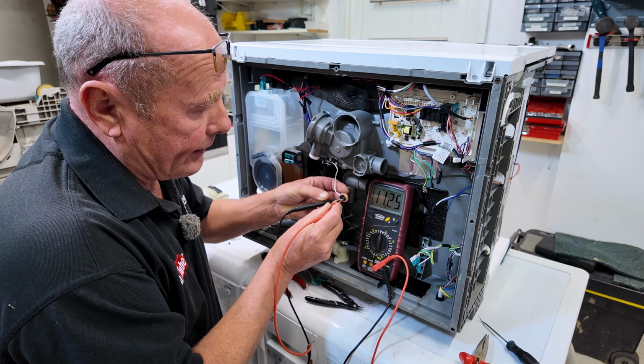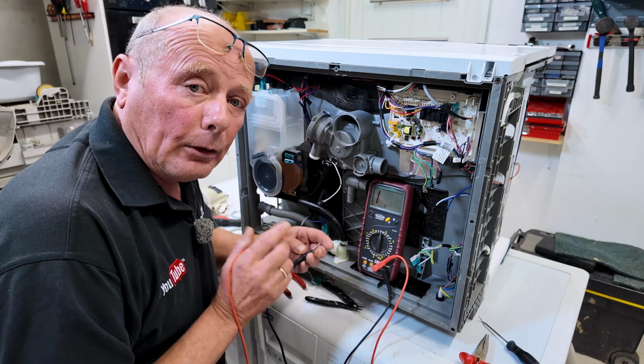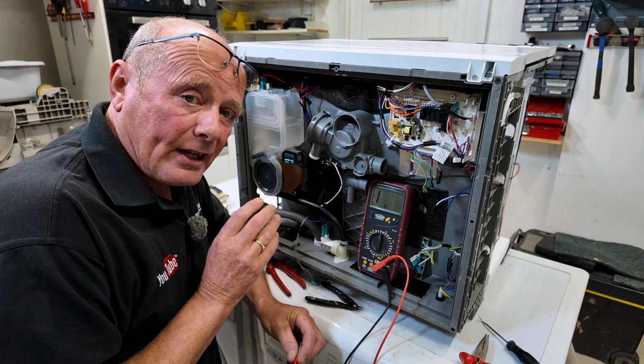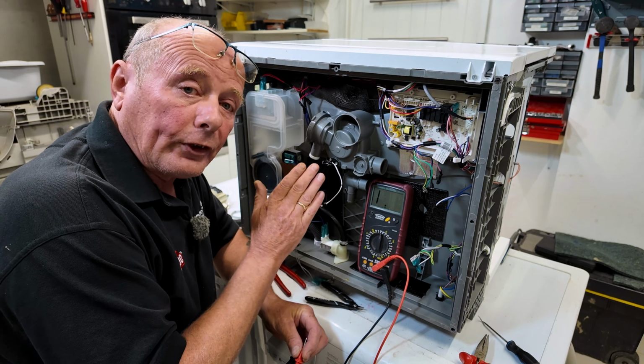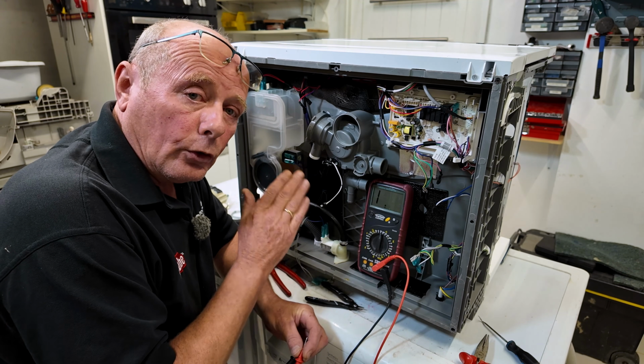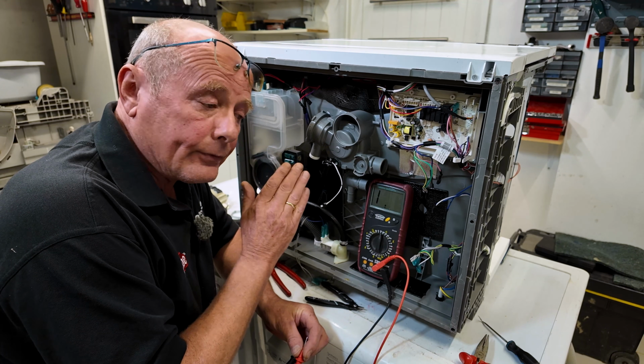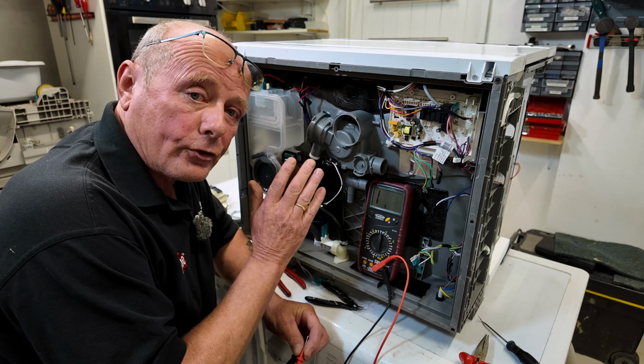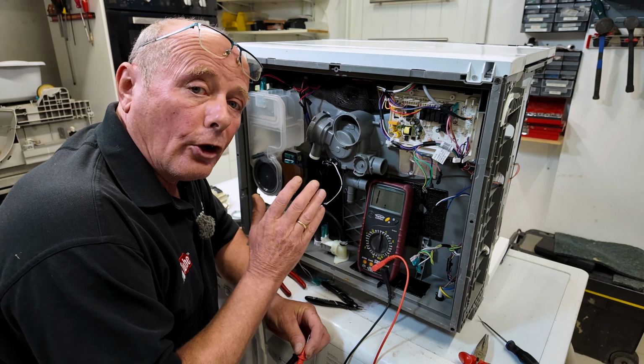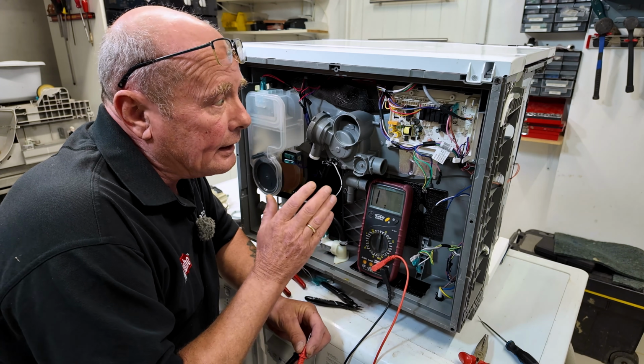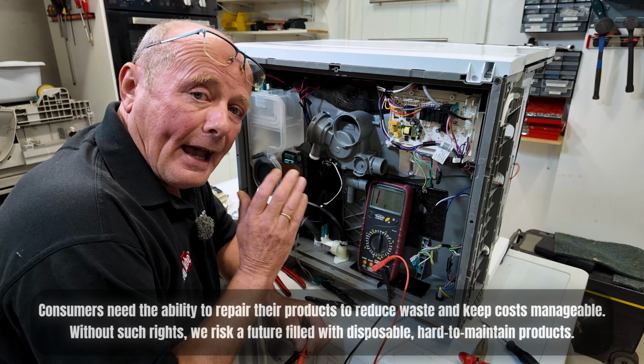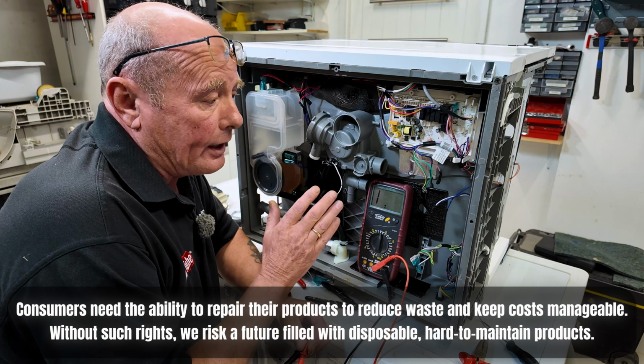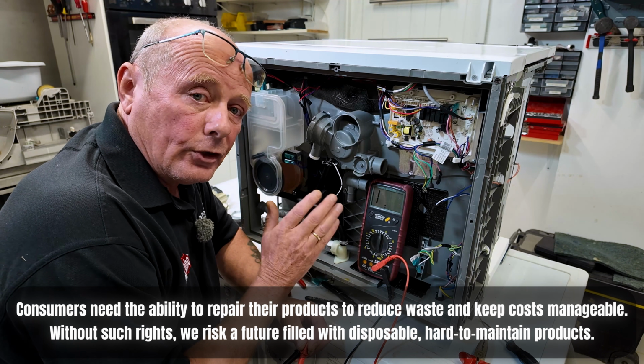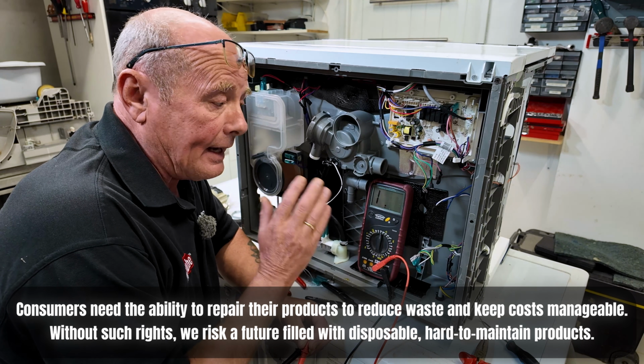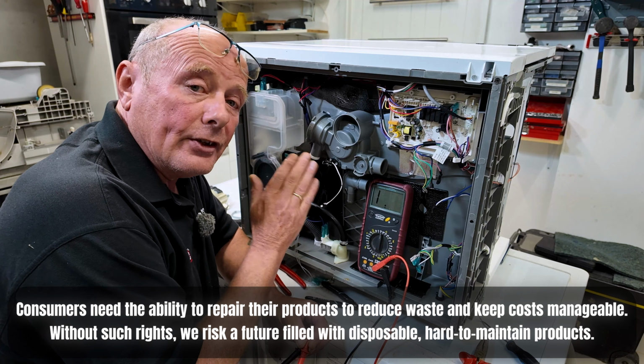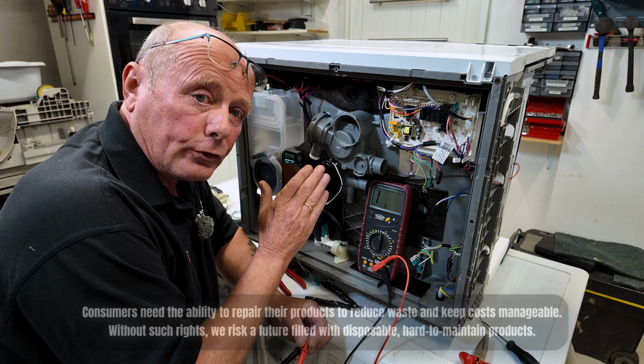It's very difficult to get these probes in, but that should help someone understand if their NTC sensor is in good condition. As room temperature changes, the NTC value will differ, but I don't have a chart to show because the manufacturer hasn't given that information - which doesn't help with the Right to Repair Act, since all machines have the right to be repaired, and without that information, the public and engineers can't check if the NTC value is correct at a given room temperature.